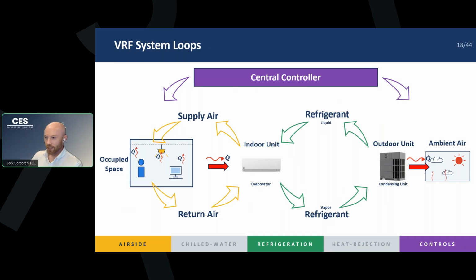And another way of kind of showing that, right? We have just our 3 system loops, our control loop, our air side loop, and refrigerant loop. Connected with our indoor and outdoor units. As you can see, both of those components are part of our refrigeration cycle, and then our evaporator is our bridge between the 2. And just in general, we're moving our heat from left to right, occupied space out to our ambient air.